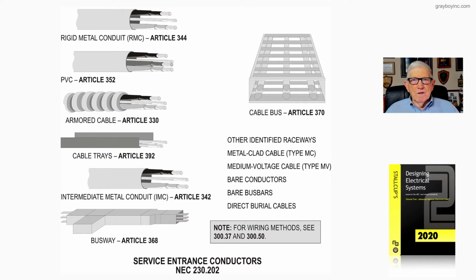And of course, you know that Chapter 3, the 300 series, deals with a particular wiring method such as rigid metal conduit, abbreviated RMC, as Article 344, etc. And you have approximately 12 or 13 wiring methods that are listed that could be used for service entrance conductors when you're dealing with high voltage. The new Article 311 also contains the old existing article for medium voltage, Article 328.